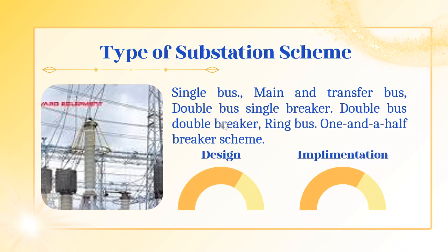There are different types of substation scheme. First, single bus, main and transfer bus, double bus single breaker, double bus double breaker, ring bus, and one and a half breaker scheme. Among all these substation schemes, the one and a half breaker scheme is very useful and convenient.